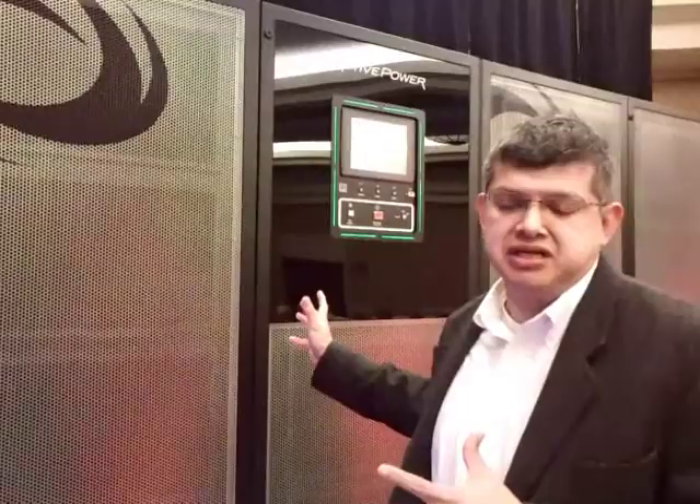We're here in one of the conference rooms at 7x24, and you guys have a demo unit. Tell us what this is and what your ambitions are for the product. The building blocks in North America for multi-module data centers have traditionally been 750 KVA — the power electronics, the size of the servers, the size of the load, the configuration with the breakers and everything else needed for power distribution. The platform we had with the 300 was not ideal for these massive multi-module functions, so we created a highly dense, one flywheel-based UPS at 750 KVA to adapt to those building blocks.